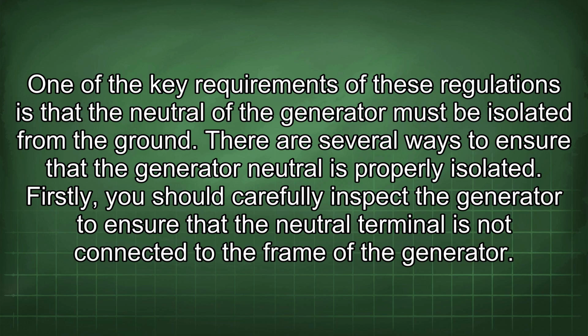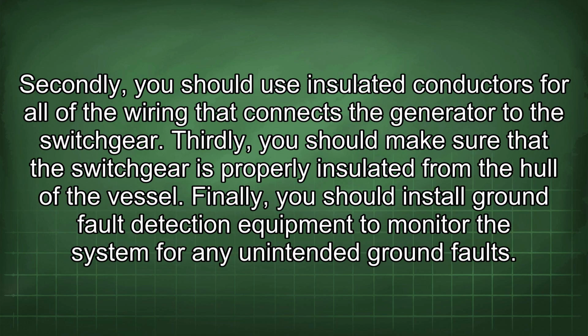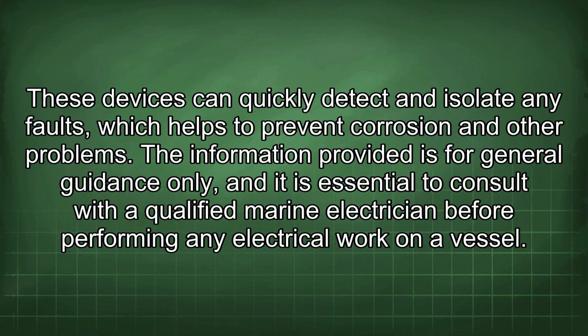Firstly, you should carefully inspect the generator to ensure that the neutral terminal is not connected to the frame of the generator. Secondly, you should use insulated conductors for all of the wiring that connects the generator to the switchgear. Thirdly, you should make sure that the switchgear is properly insulated from the hull of the vessel. Finally, you should install ground fault detection equipment to monitor the system for any unintended ground faults. These devices can quickly detect and isolate any faults, which helps to prevent corrosion and other problems.